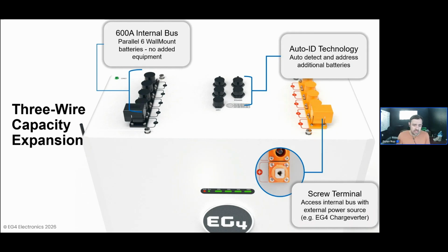And have both of those internal battery buses operate in parallel. One additional conductor is required for communications, but again, as we talked about earlier, because of the auto ID technology on site, there's no additional action needed aside from simply plugging those conductors in to the appropriate batteries in the appropriate ports to get those things communicating and identifying the batteries that are on site and ensuring that they communicate and can cooperate with each other to provide a single battery bank for delivery to the inverter. And then finally, there is a screw terminal, which is attached to that same internal bus of the battery system.